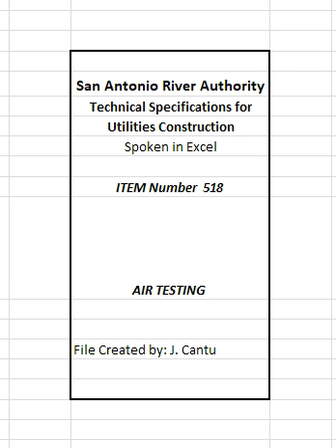D equals average inside pipe diameter in inches. L equals length of line of same pipe size being tested, in feet. Q equals rate of loss, assume 0.0015 cubic feet per minute per square foot internal surface shall be used since a K value of less than 1.0 shall not be used. Allowable test times for selected type pipe less than 36 inches average inside diameter is shown in a table. The heading titles are: pipe diameter, minimum time, length for minimum time, and time for longer length.